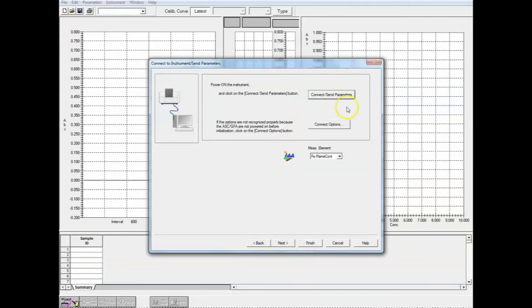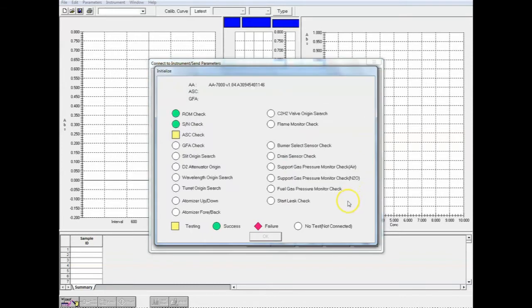Okay, now that we've put all that information in, now we're going to send that information to the machine. So by hitting Connect Send Parameters, it transfers that information to the actual instrument. So I've already turned the instrument on, and I've turned on the gases, the gas tanks that are connected to it that supply the fuel. Okay, so that's already done.